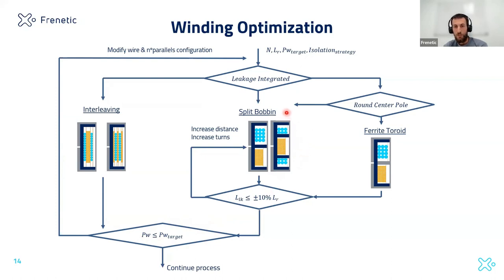There is another option, which I saw here: if neither of these approaches is enough to get the leakage that you need, there is an option to put some ferrite material in between the windings to increase the leakage flux and the leakage inductance. This is not for free. At the end, we are putting ferrite material, so we are increasing the complexity of the manufacturing, we are increasing the complexity of the modeling, and we are adding some losses here, but it's a very effective solution to have a higher leakage flux and a higher leakage inductance.